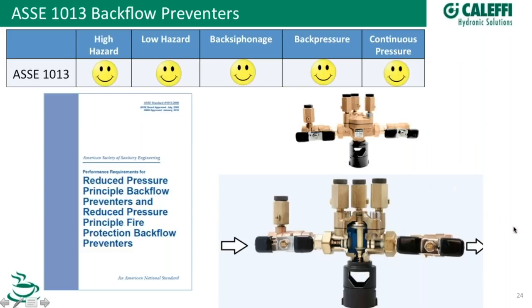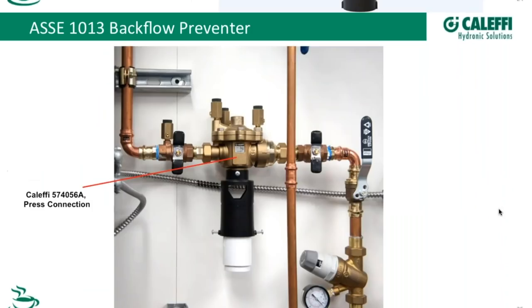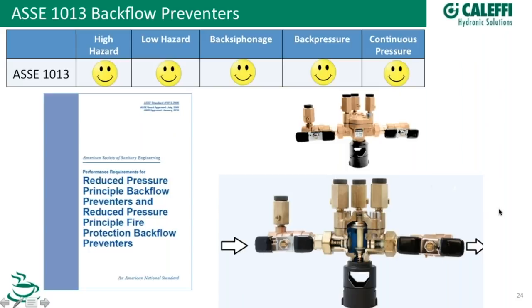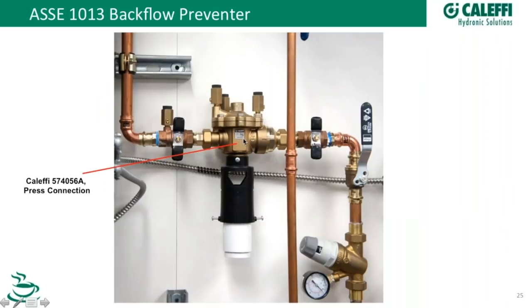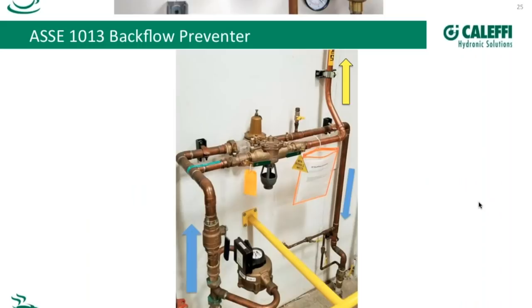The question with boilers is which one do I need on a little residential boiler? One issue is that someone down the road might squirt a chemical in there, and that would need a high hazard preventer. That's why requirements are getting tougher on having higher hazard protection on boilers regardless of pressure level. Even if it's under 30 PSI, more and more authorities having jurisdiction are saying you've got to go a step above. And obviously that's going to take more cost, and it becomes something that has to be officially tested, recorded yearly in Wisconsin.